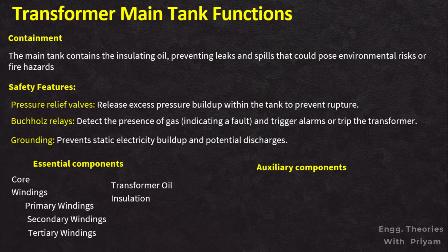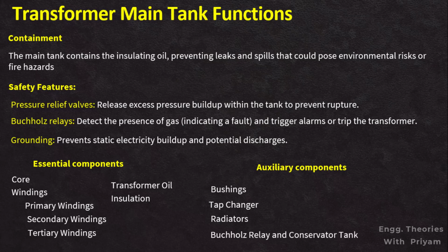The auxiliary components. There are other auxiliary components that can be fitted inside the tank depending on their voltage and the nature of use, although some of those components are mostly installed outside the tank for high voltage applications. Bushings are placed on the top of the tank. The tap changers are placed on the secondary winding inside the transformer's main tank. The radiators are attached outside the transformer's main tank on two opposite sides. The Buchholz relay and the conservator tank are attached outside the transformer main tank with the help of a pipe connecting them to the tank. The pressure relief valves are placed on the top of the transformer's main tank, and the grounding system and explosion vent are also placed on the top of the transformer tank.